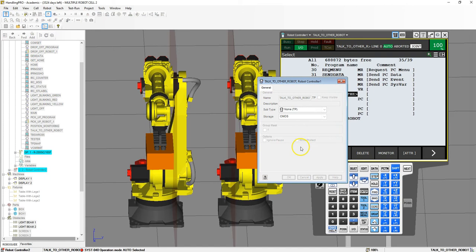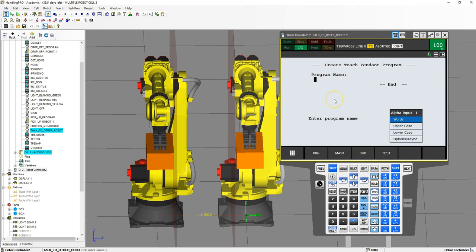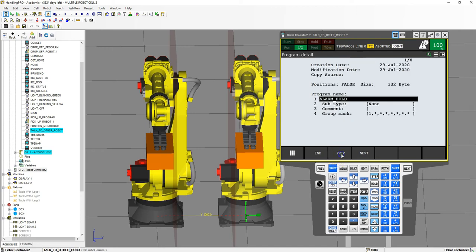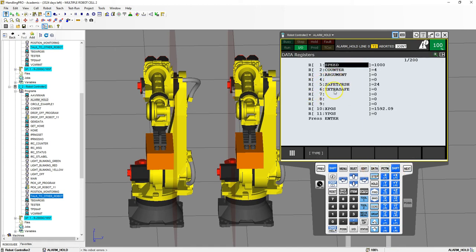Now let's create the program that will make the robot hold if it's about to go into the unsafe position. We create a new program in robot controller two called 'alarm_hold.' In the detail settings, we set the group mask to asterisks because there will be no motion — it's going to be purely code. We also set up an extra safe position register (register number six) in the data to give a little more buffer beyond the threshold, making sure we're not even close to that boundary.